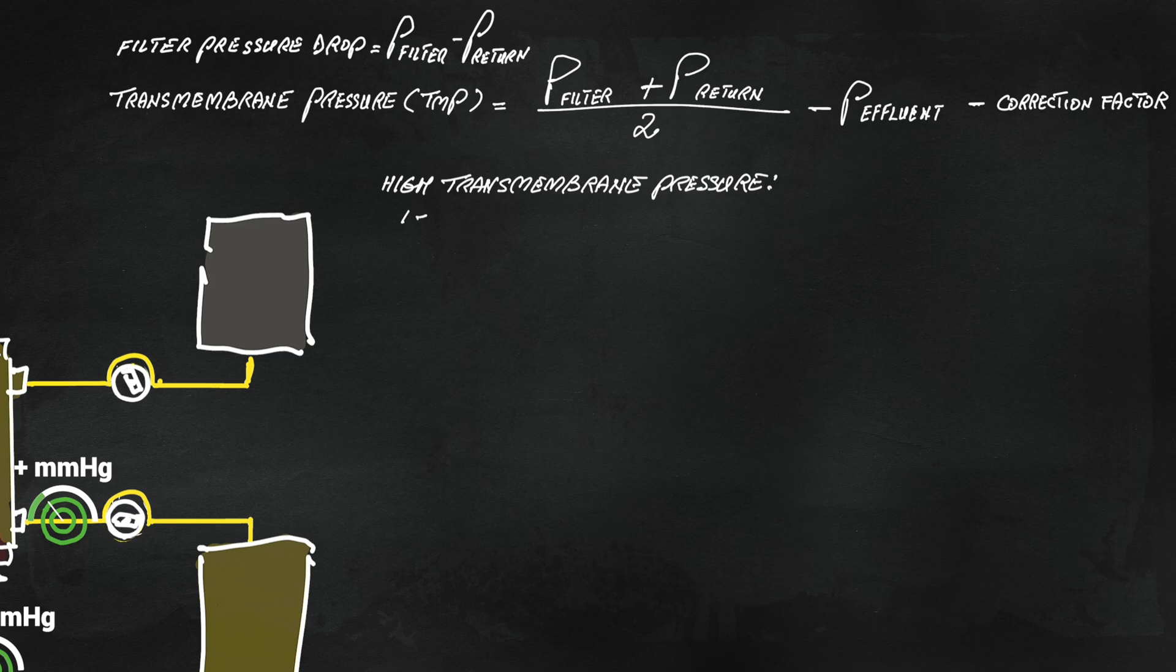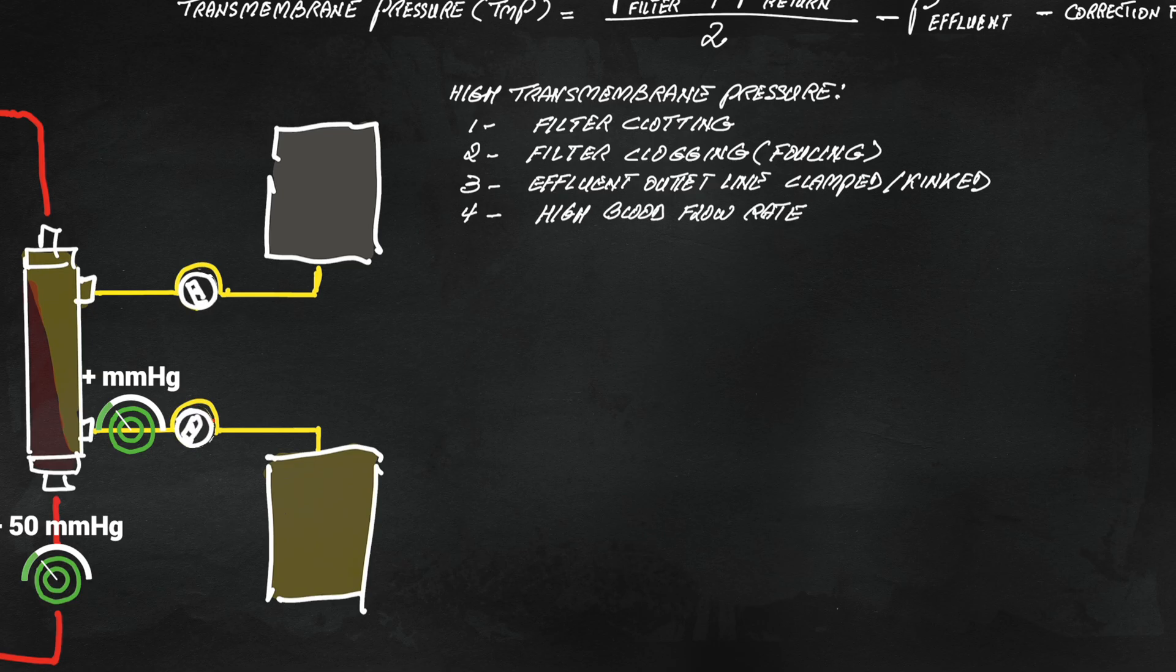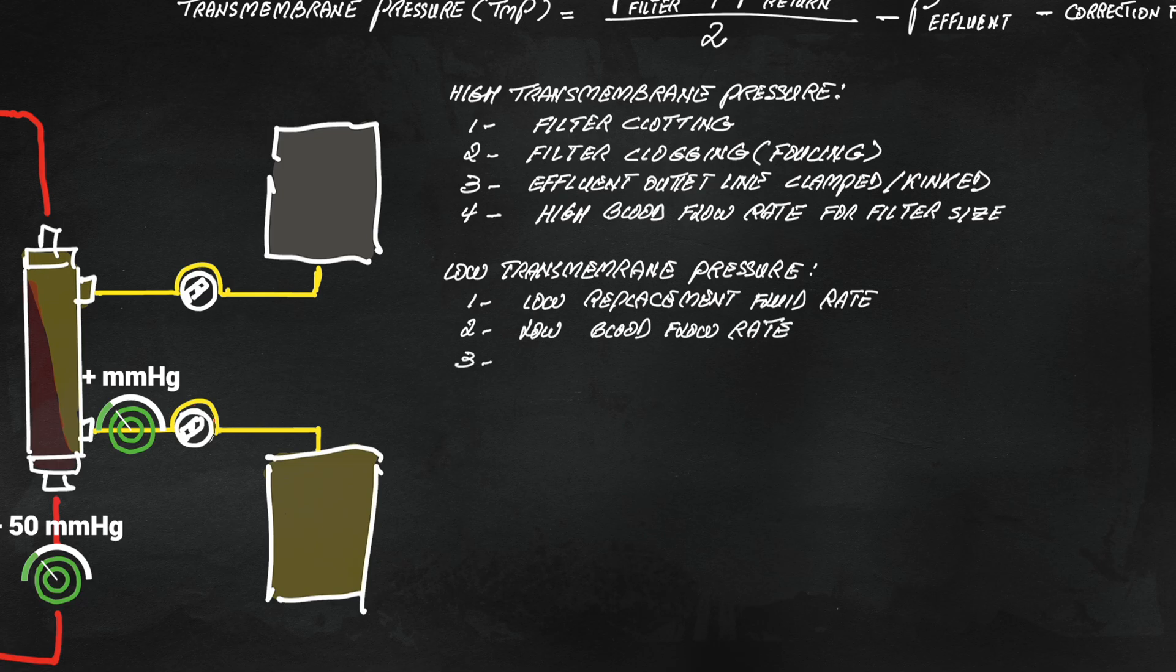Transmembrane pressure is helpful because it trends upwards with filter clotting or membrane fouling, or in other words, clogging. Transmembrane pressure can drop due to membrane leak or pre-filter infusion due to lowering in blood viscosity.